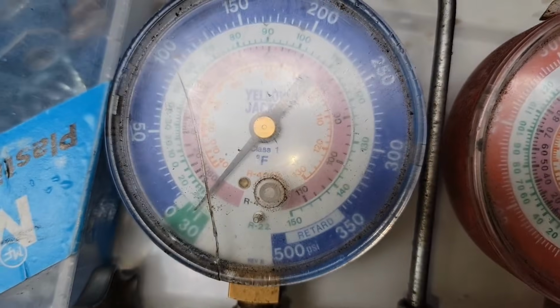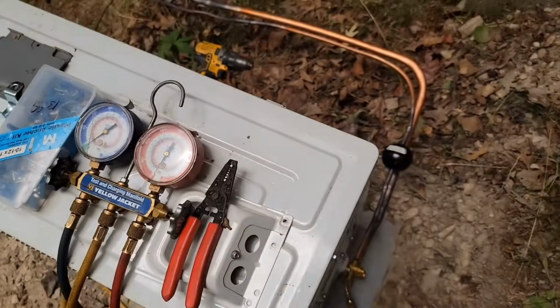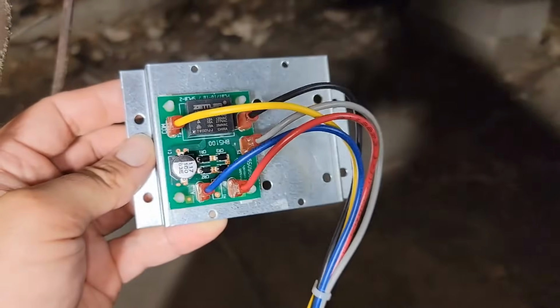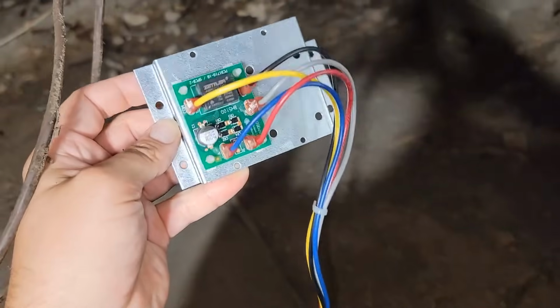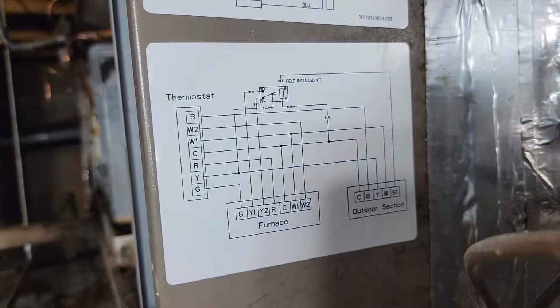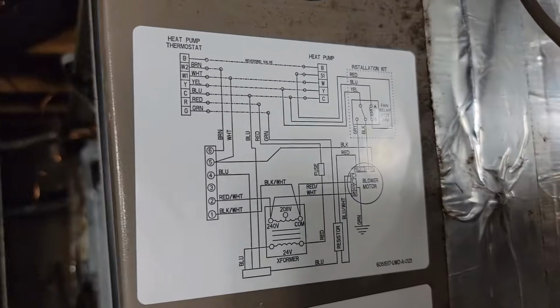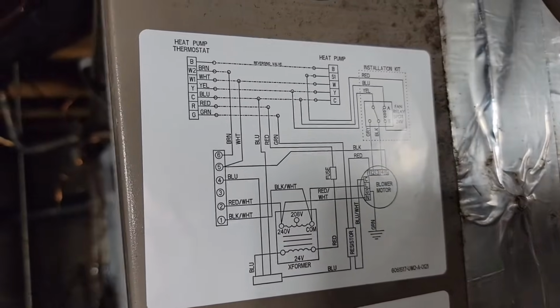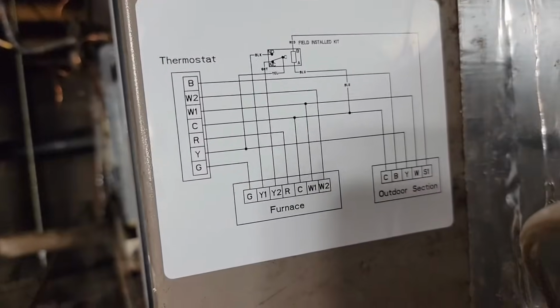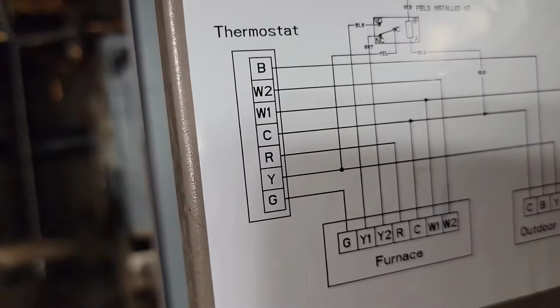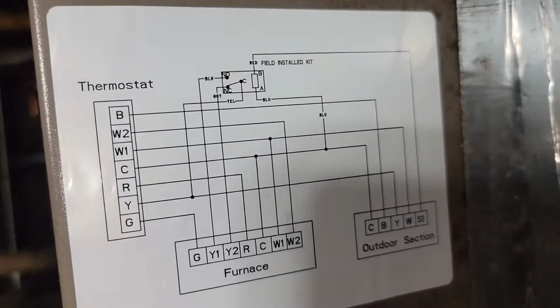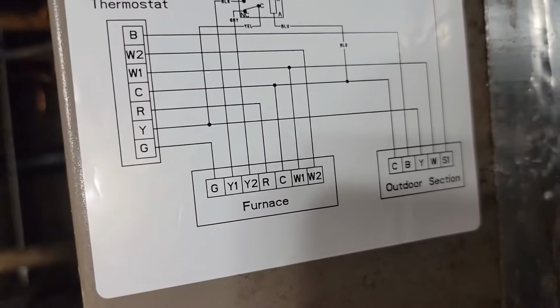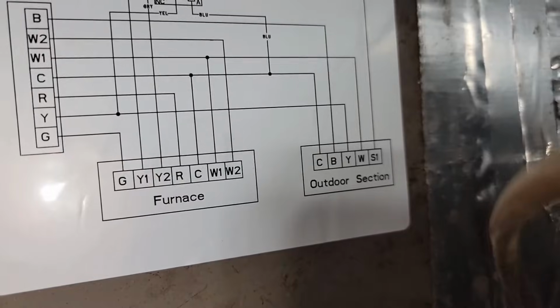Looks like it's pulled down into a vacuum. Good deal. Now I'm going to mount this little plate that holds the relay and then hook up the wiring. I've got wiring diagrams that were included in this installation kit. If you want to stop, pause the video, and take a look at these, you can. We already wired up the thermostat, so now all we have to do is wire up this relay with the furnace wiring and then the outdoor section.